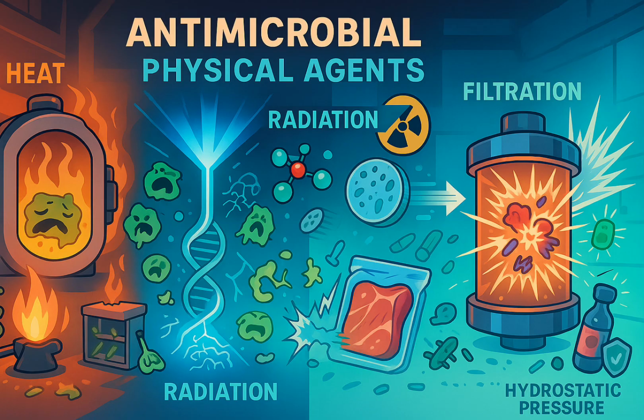Not the pressure itself. The pressure is just the tool to allow the water to reach that superheated state without boiling away. Precisely. At normal atmospheric pressure, water boils at 100 degrees C. Increase the pressure, you increase the boiling point. You need that 200 kPa partial pressure of steam to hit 121 degrees C. And this reveals why getting the air out of the autoclave chamber first is so critical. Why is that? If air is trapped, its partial pressure adds to the total pressure inside, so there's less room for the steam's partial pressure to build up. You won't reach the target temperature needed for sterilization. You won't hit 121 degrees C if there's too much air left.